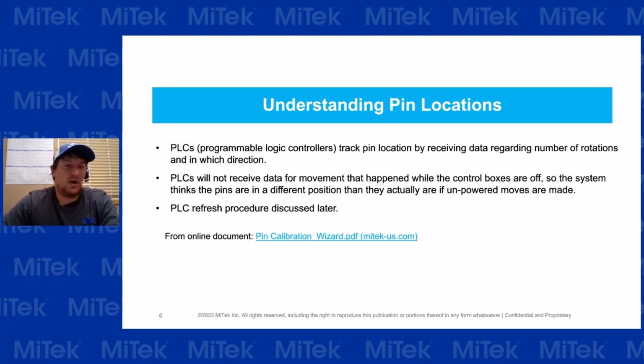If the control boxes are off and the pins move manually, like I said earlier, it won't know where it's at. So you have to recalibrate with the box on. That's the only way you're able to recalibrate, is with the box on. So any unpowered moves, they're not picking up location. A lot of times PLCs will go to sleep in our Gen 3. There's a refresh procedure that I will discuss later. And then at the bottom there, you see a document with pin calibration. Click on that. It's a link you can go right to the source and read through this just a little bit further.